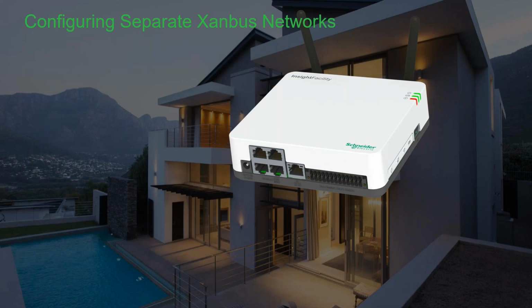6 XW Pros takes up a significant amount of bandwidth for a single Xanbus network. You'll easily have enough extra bandwidth to add a battery monitor, an AGS, and a system control panel. However, you will not be able to add several charge controllers to the same Xanbus network as the 6-inverter stack. For large DC-coupled systems such as this, use the secondary Xanbus network of Insight Facility, which will aggregate the devices from both Xanbus networks to a single web page on Insight Local and Insight Cloud.